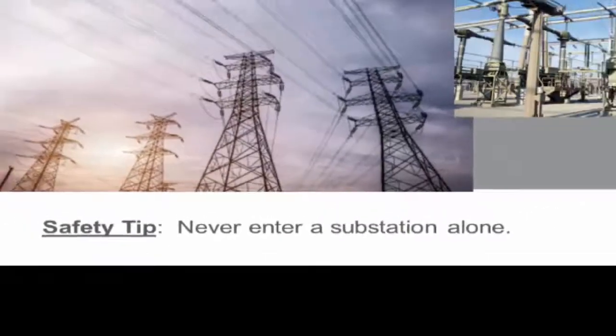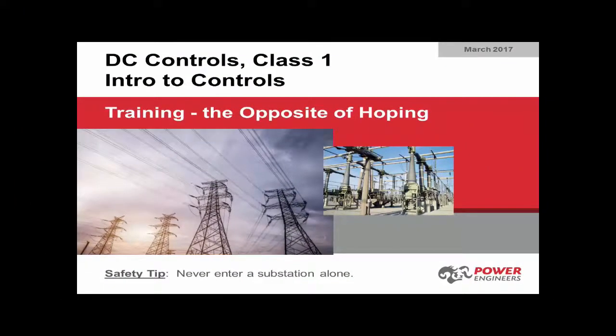Today's safety tip is to never go to a substation alone. Substations are not inherently safe places, and if you went alone and got hurt or incapacitated, it's hard to know how long you'd be there before someone found you. Also, if something bad happened in the station, maybe not hurting you, but say a breaker inadvertently tripped, it's good to have another person to back you up on exactly what happened.